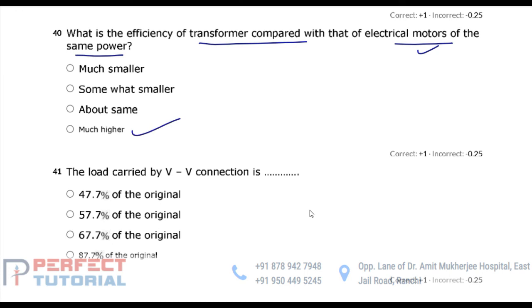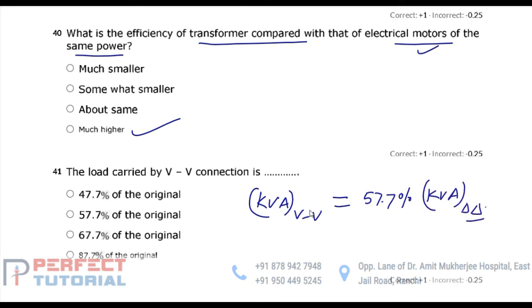Next सवाल है the load carried by V-V connection is. So load carried by the V-V connection, say KVA rating of V-V connection or open delta connection is equal to 1 by root 3 times or 57.7% that of the KVA rating of delta connection. So original connection समझेंगे delta connection. अगर एक फेज रिमूव कर दिया गया प्राइमरी और सेकेंडरी साइड ऑफ द डेल्टा कनेक्टेड ट्रांसफार्मर से, then obviously आप पाएंगे V-V कनेक्शन. And जो V-V कनेक्शन obtain होगा, V-V कनेक्शन जो लोड कैरी कर सकता है without overloading of any of the single phase transformer, that loading would be only 57.7% that in case of delta connected transformer. So answer would be 57.7% of the original.